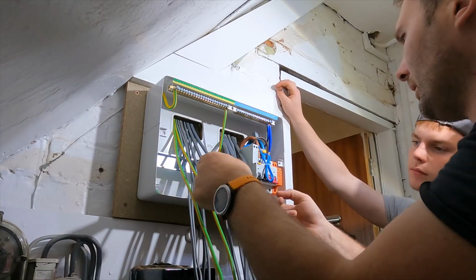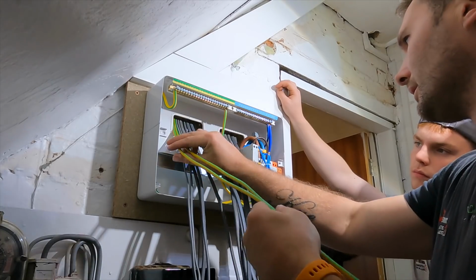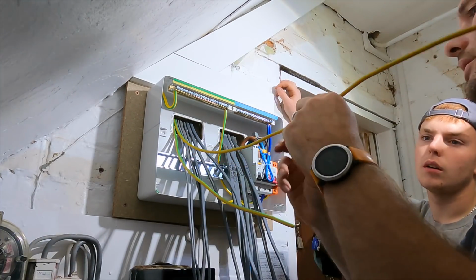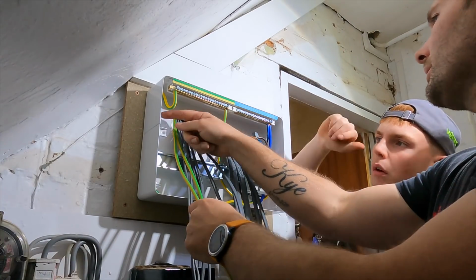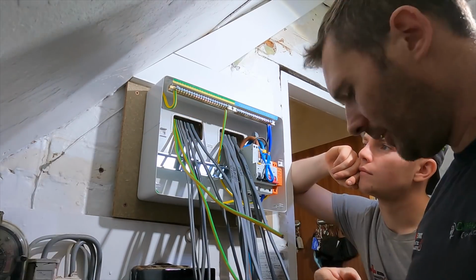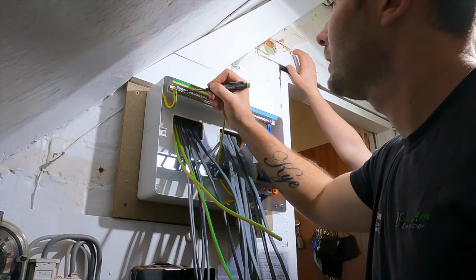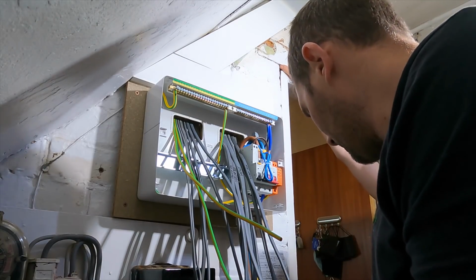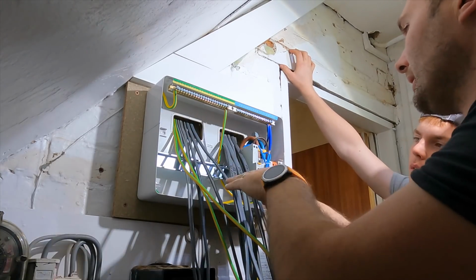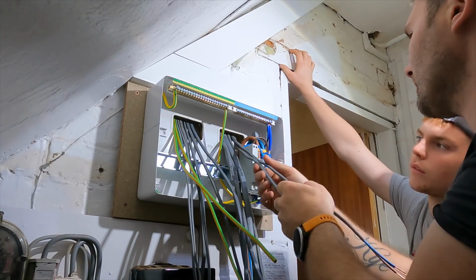So that being said, once you've got all those in, then you can get your busbar in across. And it's very important making sure you actually get those in correctly. But what I would do first is get these gas and water bonds out of the way. Now I have marked them up. So G's for gas, W for water. So what I would do is dress them in neatly. So try and match all your swoops there. And then just right hand, you can just put an M for main. And then obviously G and W for gas and water. So get those in, get them out of the way. And then basically work your way through, put your blanks in, and then you can get your busbar in. And then you can get all this started, stripping in.